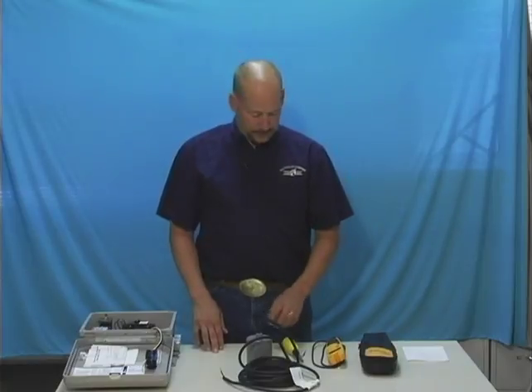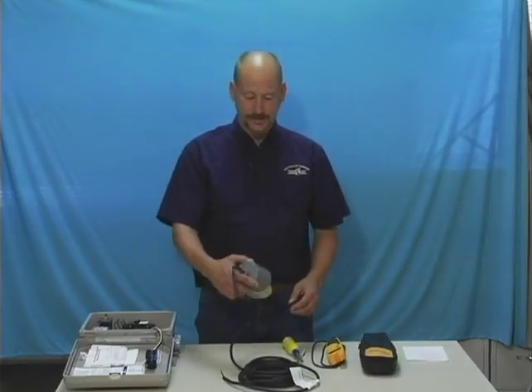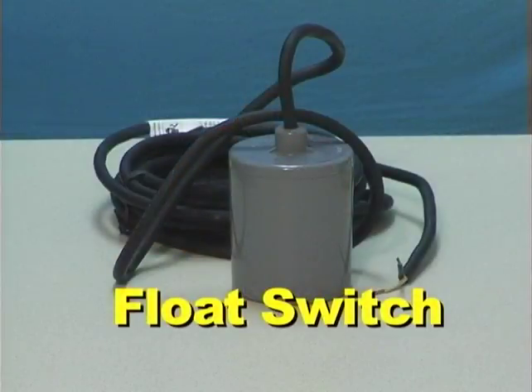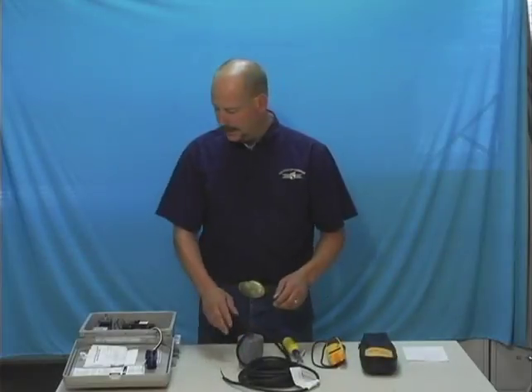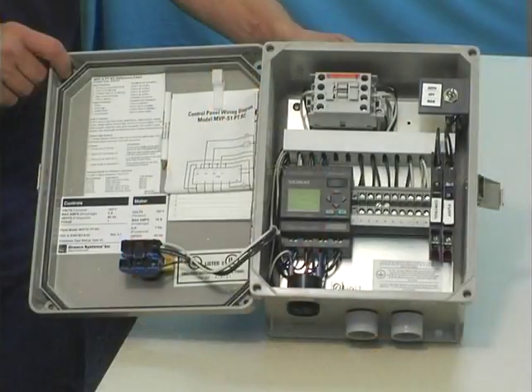Some of the things that can go wrong with the control panels are, of course, the float switches, so you're better off to have a few spare floats with you if you are going out to troubleshoot a control panel. And then the control panel itself, if you know what model number it is, that makes it so much easier if you actually take one of those out into the field, so you've got some spare parts off the control panel that you can get the customer up and going, and then later build them out for the accessories that you took out of the panel.